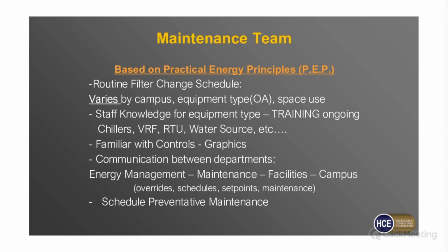A lot of the things y'all are going to really be focusing on is making sure that your filters are routinely changed, because as they get loaded up with dirt, the static goes up, so the energy goes up. This is going to really vary a lot campus by campus and equipment type—your outside air machines may have to be changed more frequently than your space use equipment.